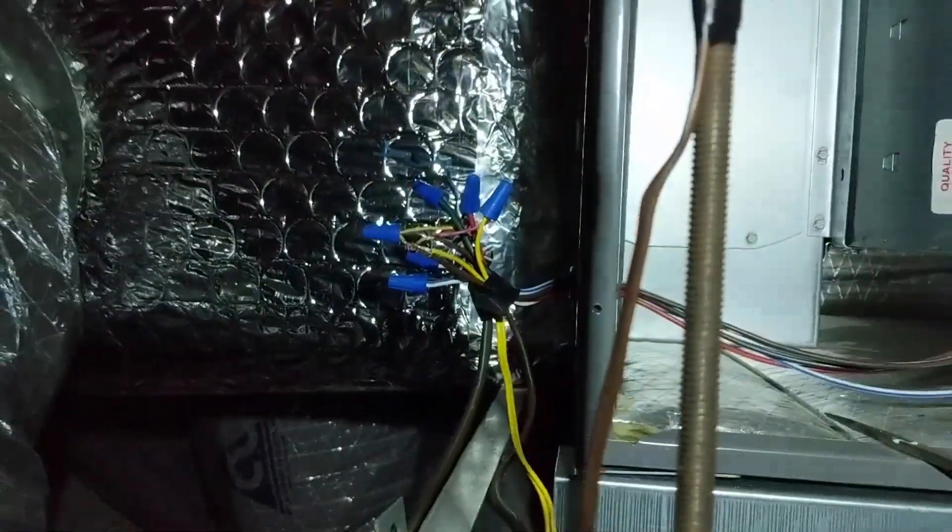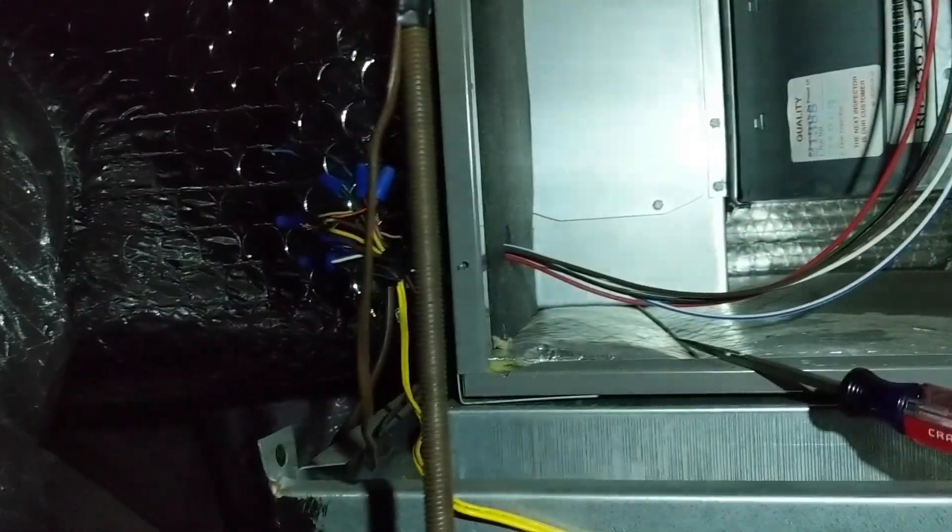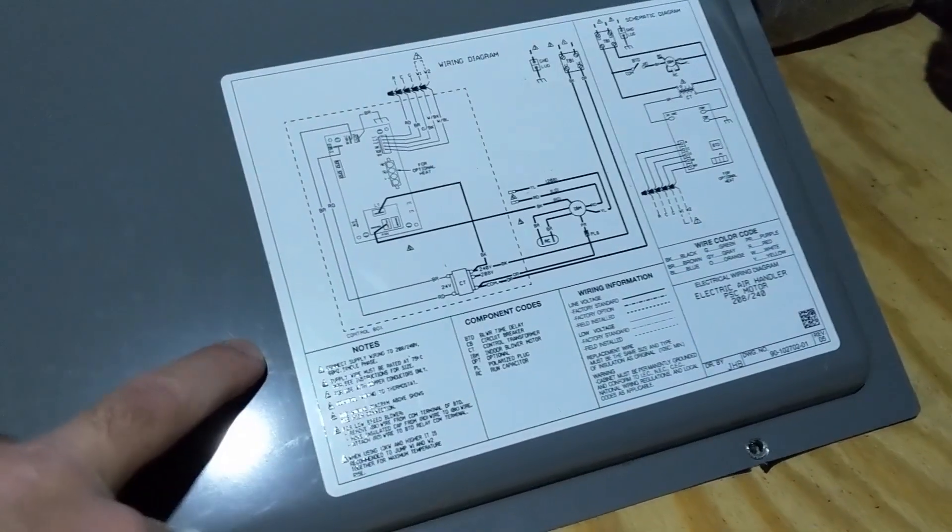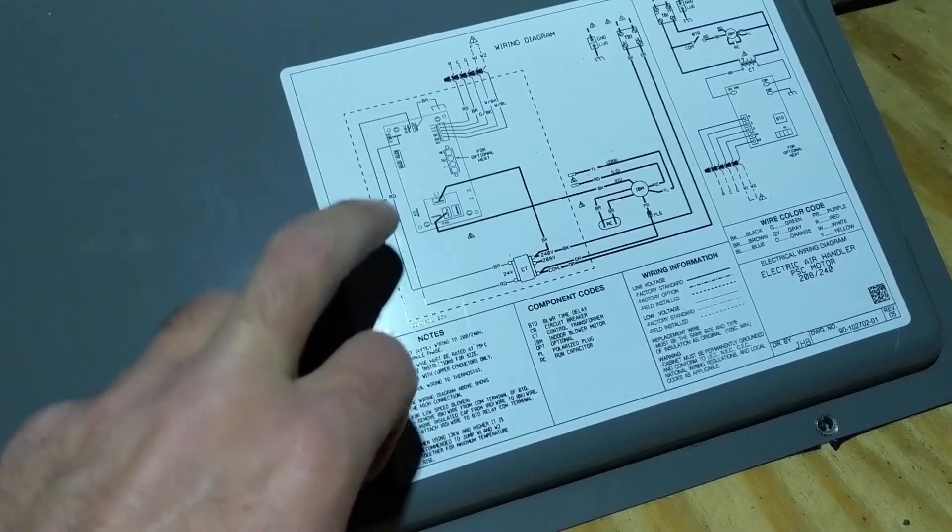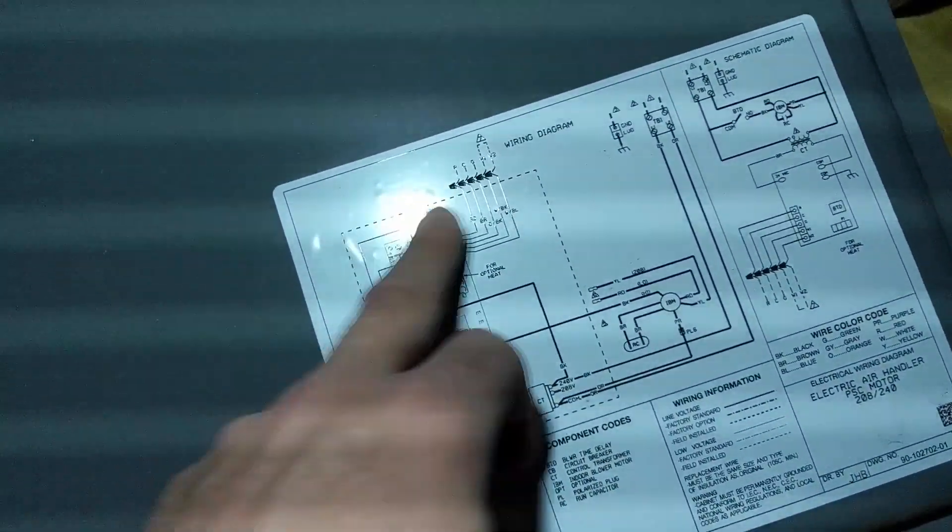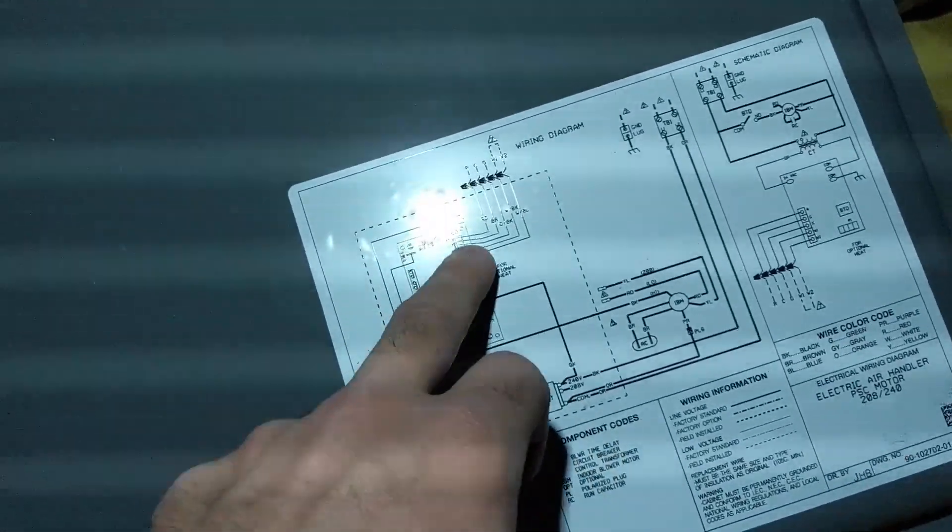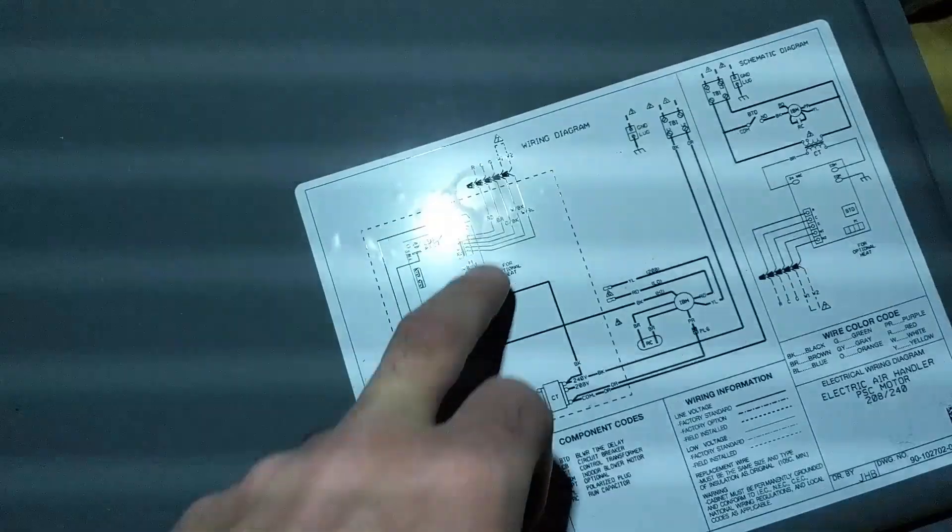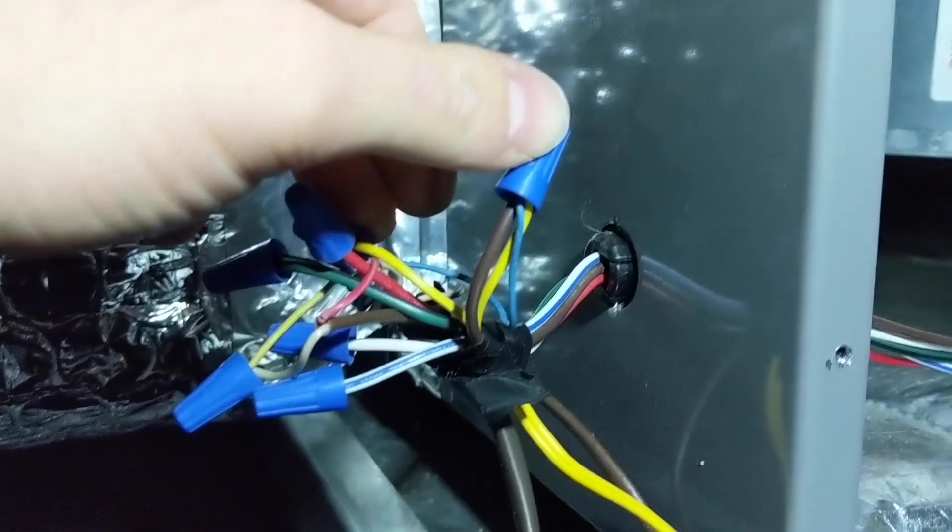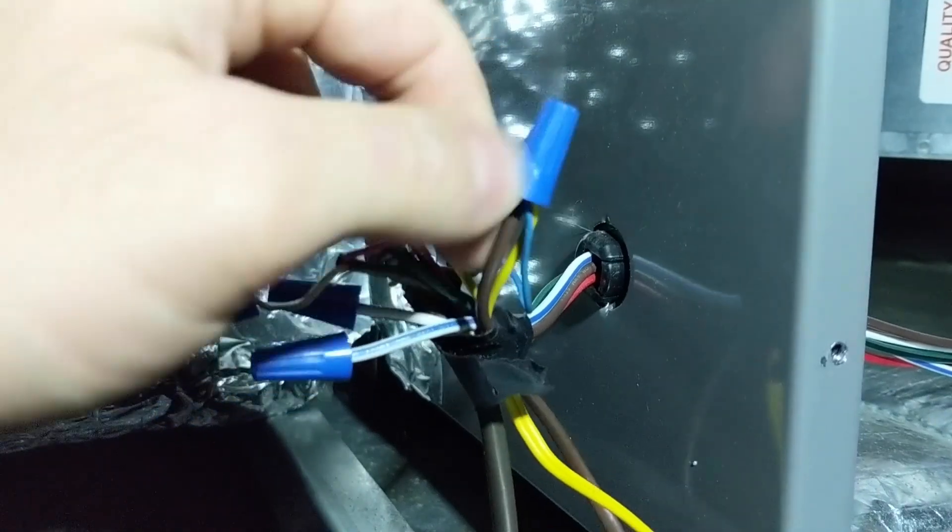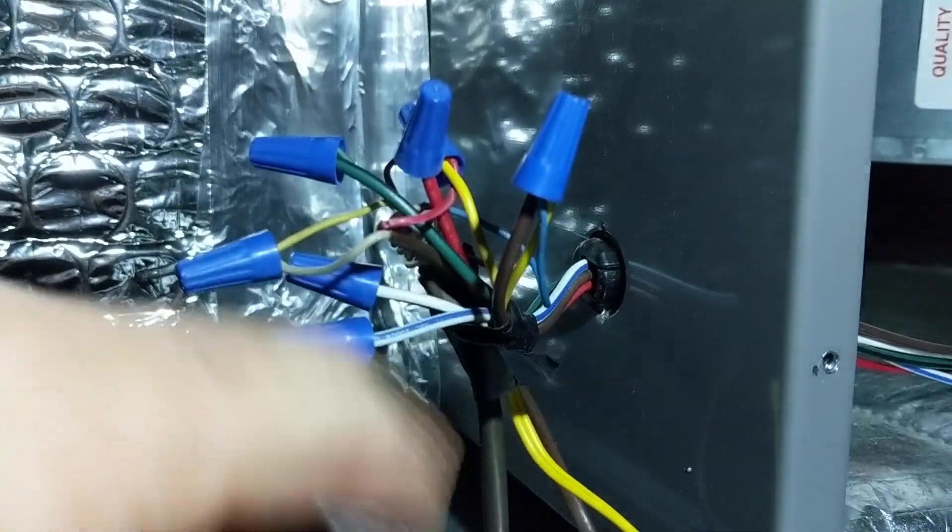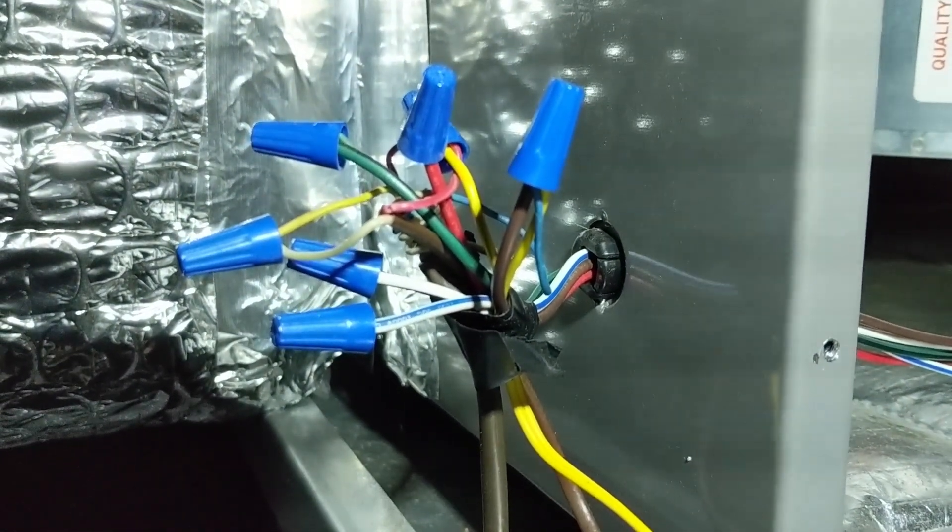This panel was removed. It should have all your wiring diagrams on it which will help you figure out which wire is your common. This is all from the control box. This is a wire coming out of the control box to a common, so the brown is your common. The wire is stripped and now connected to this brown which is the common coming out of the AC unit. We're gonna go back downstairs, connect the wires to thermostat, hook up the thermostat, and see if we get everything to work.